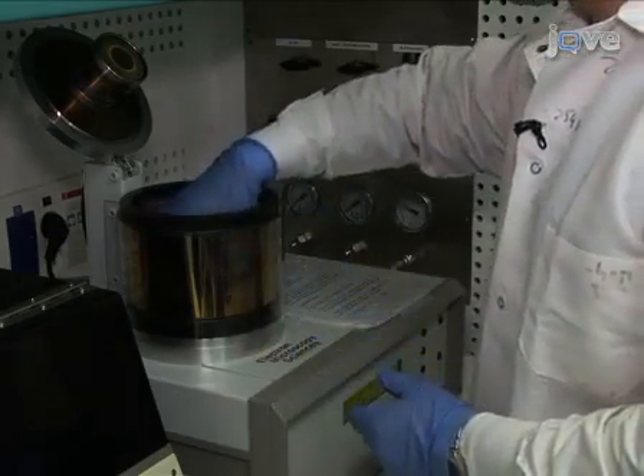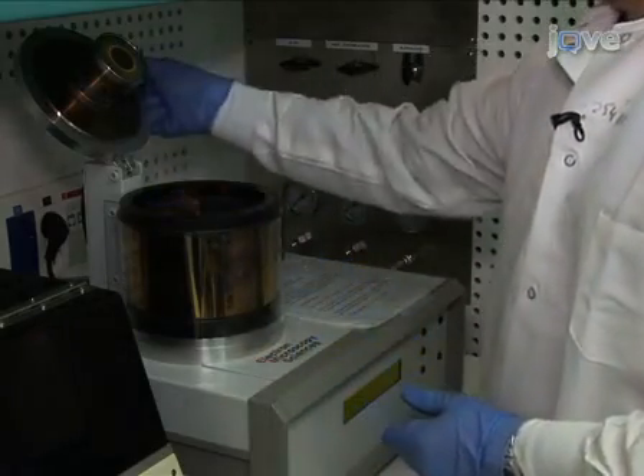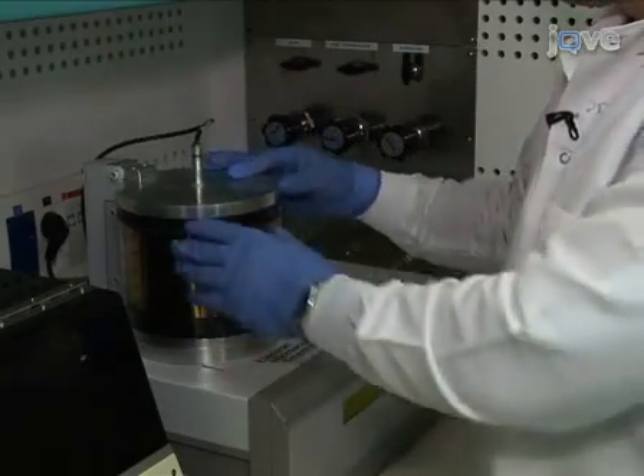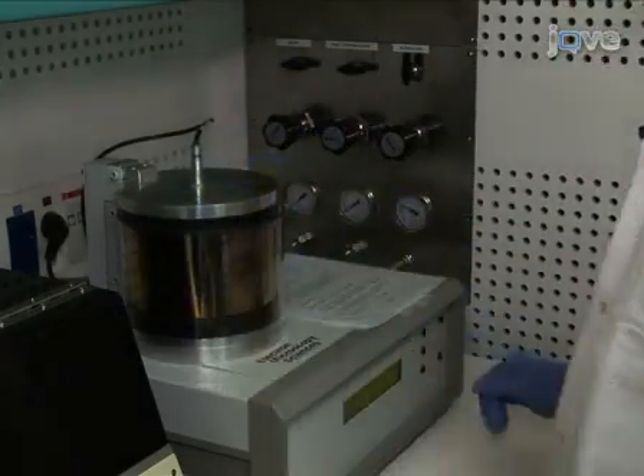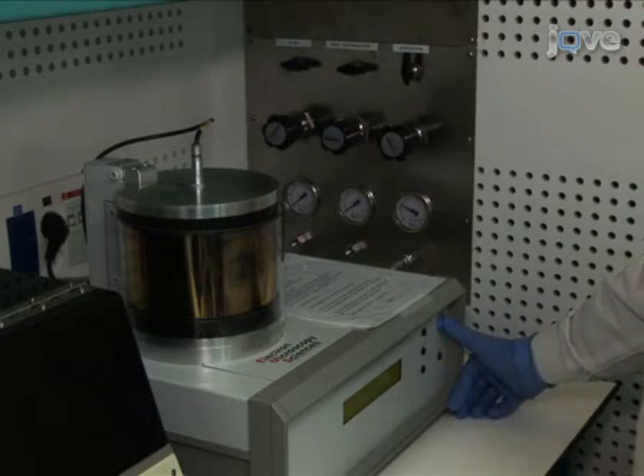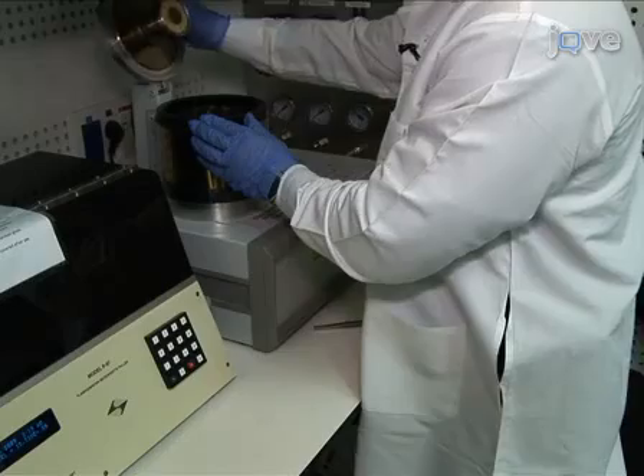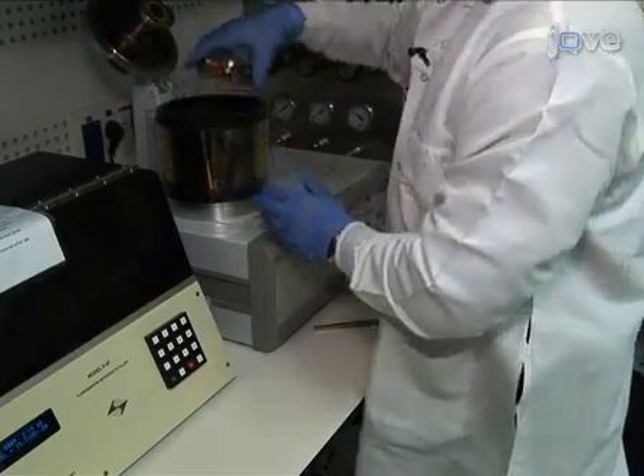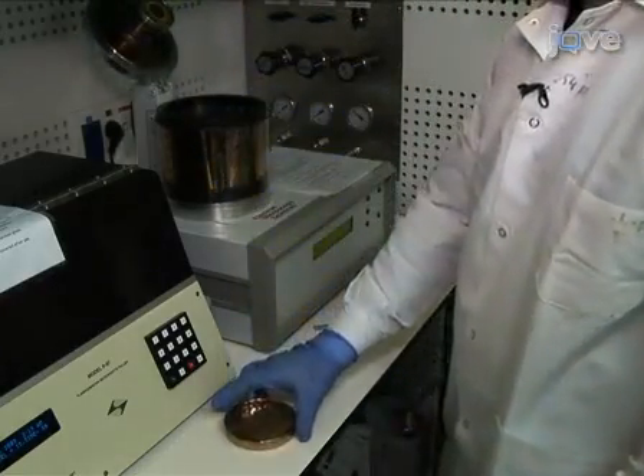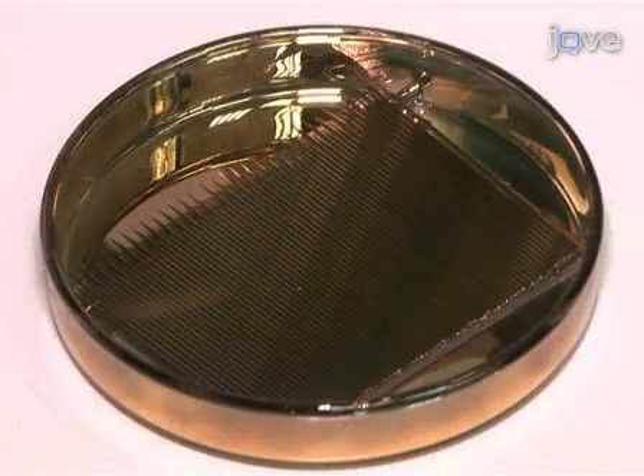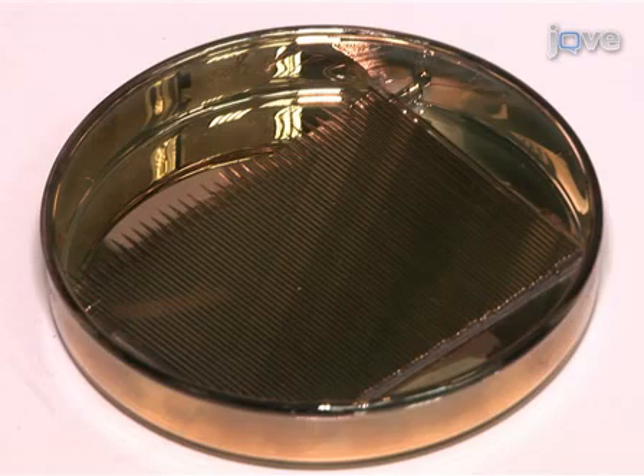Next, coat the capillaries with gold. Insert the plate into the gold sputter coater. Make sure that the gas supply is chosen according to the manufacturer's instructions, and activate a predefined coating cycle. The coating is repeated 3 to 6 times, until the capillaries are evenly golden. Once the capillaries are ready, proceed to calibrate the mass spectrometer.